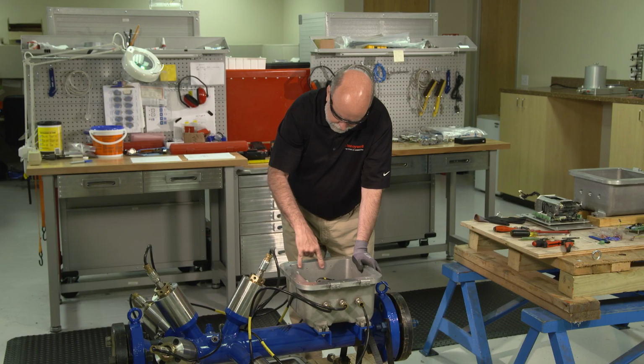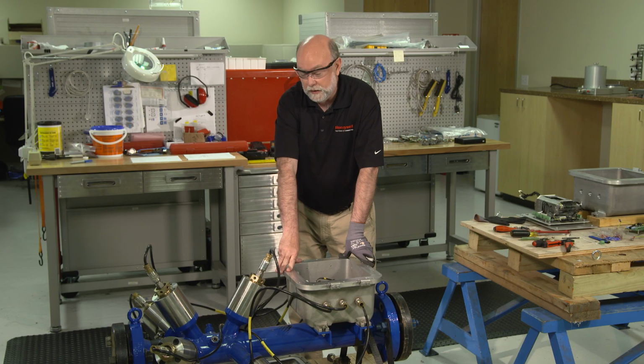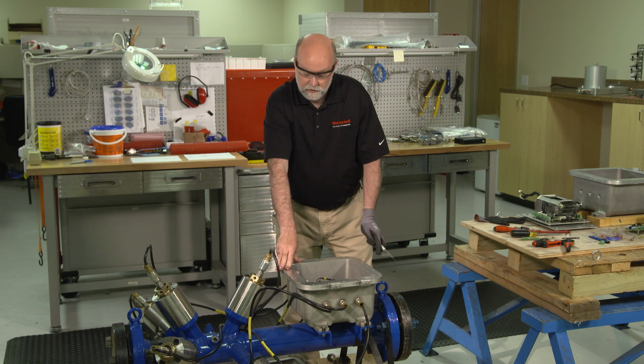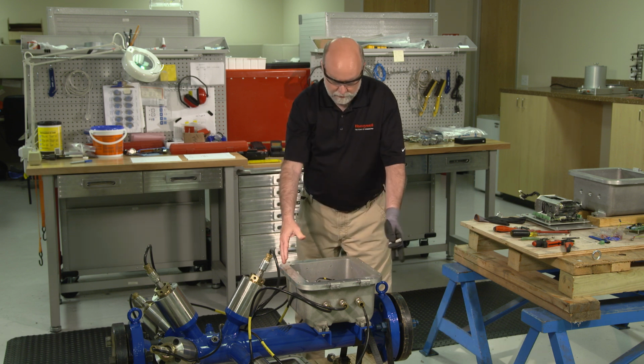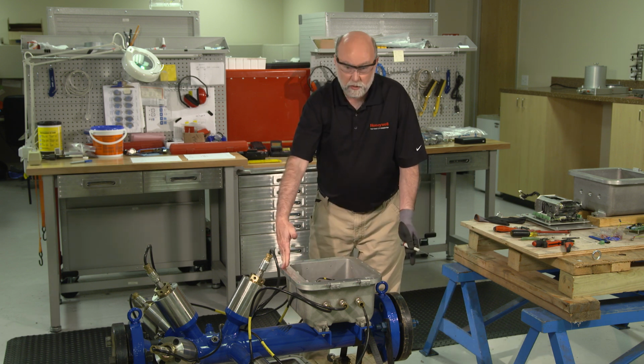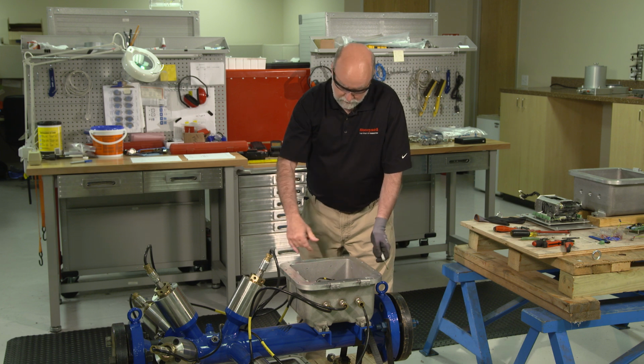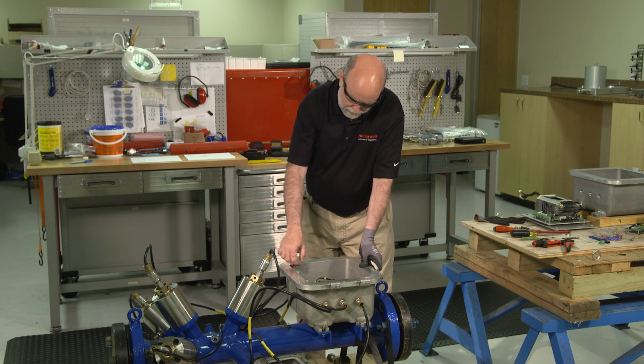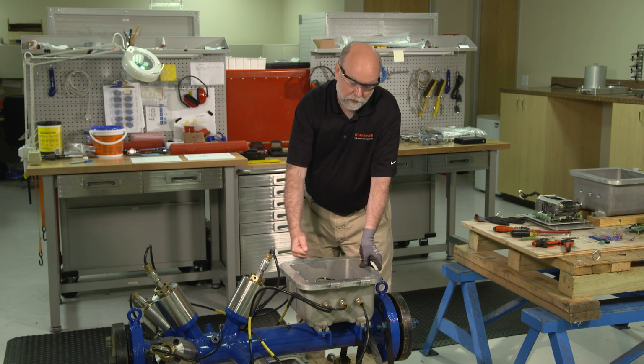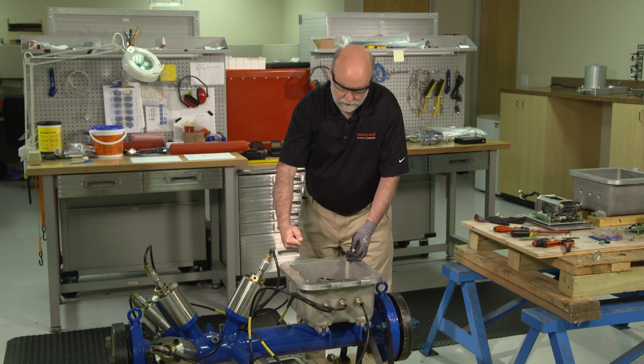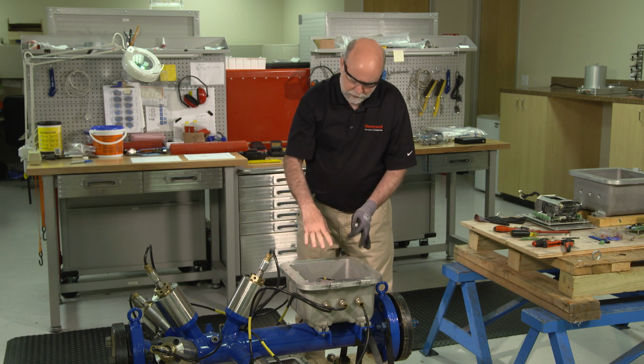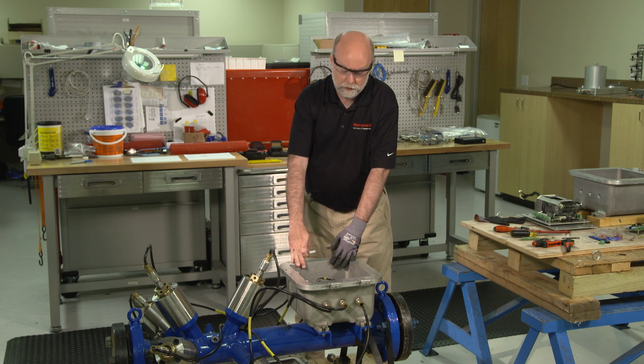Normally the box has some screws here. This is a Q.sonic 3 box, a 3-path meter. A Q.sonic 5 box for a 5-path meter is the same width but rectangular, so it's a little bit longer. That box has 3 holes on this side with a tie wrap mount here that was put in there so you could tie down your wiring. We're going to remove those screws. We're going to have some different kind of hardware that goes in there on the new box.